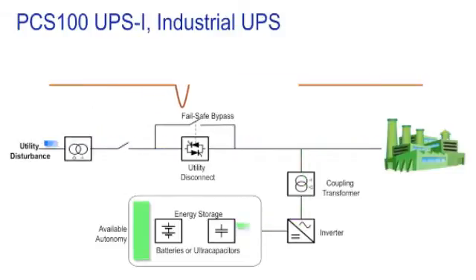When the UPS-I detects the sag, the inverters start. The customer's load is supported via the inverter's output, taking direct current from the capacitors and inverting it to a perfect sine wave to supply the customer load via the coupling transformer.